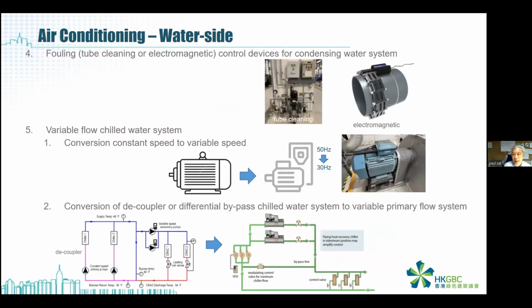Another one: Hong Kong has soft water, not hard water, but I know that in most other countries or cities the water is hard water. So calcium carbonate is a fouling contaminant that always affects systems using fresh water. They would use tube cleaning, or some electromagnetic clamping on the pipe works. For example, with automatic tube cleaning, there are spongy balls running along the condenser tube that clean the foulings or calcium carbonate.